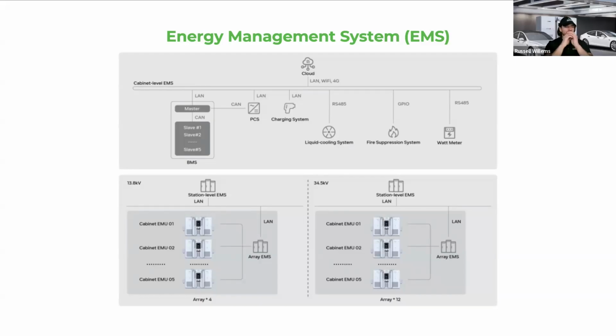When you have multiple E-stands distributed across a segment, there's the flexibility for the AC combiner and the EMS control system to flow charge from one set of batteries to another. Say you have two or three E-stands distributed across parking spots, and one happens to be the easy pull-straight-in spot getting a lot more consumption. Instead of just pulling from the grid, our EMS system can communicate across the batteries and send power from one battery if the setup allows for it—something we pay close attention to. During single-line reviews we confirm whether a given setup enables this; as long as there's an AC combiner, we should be able to do it.